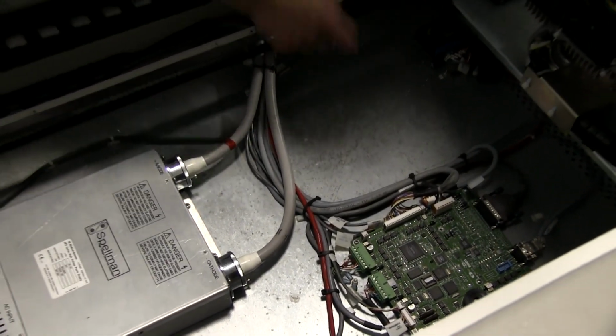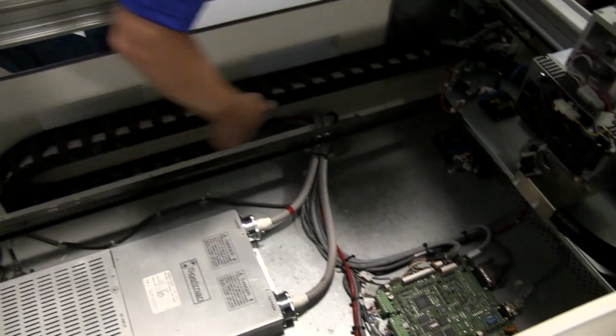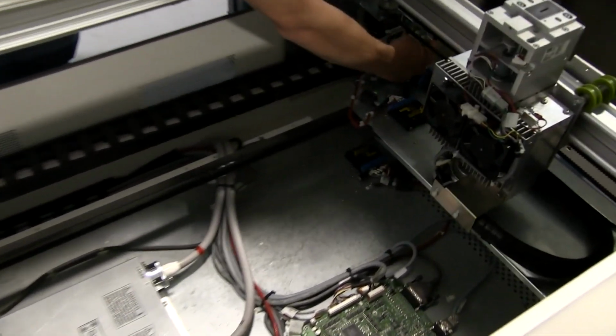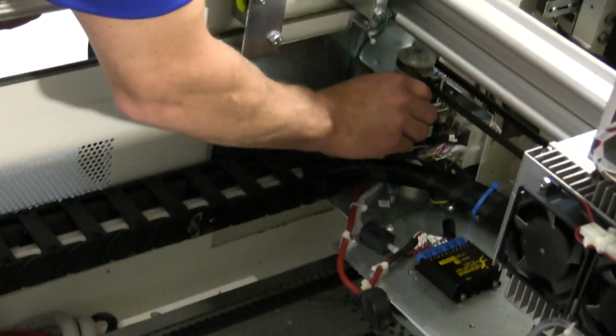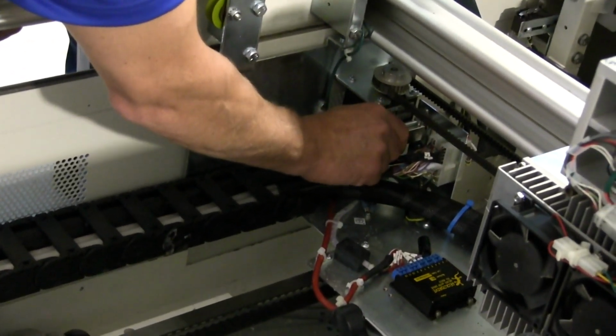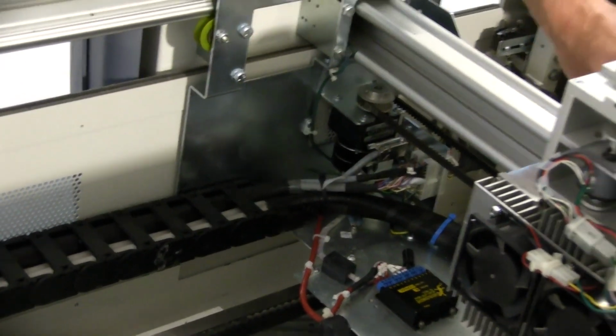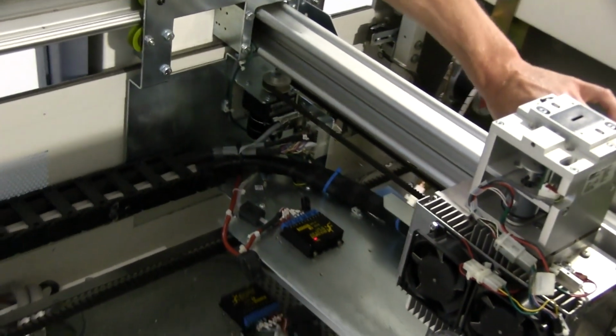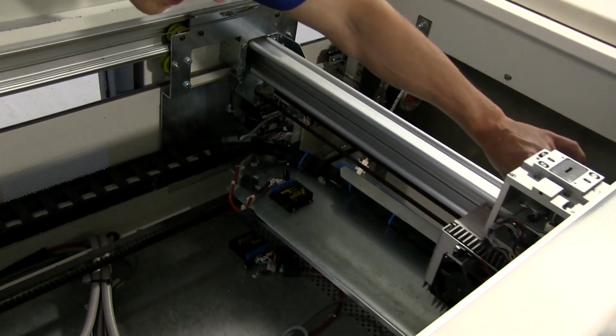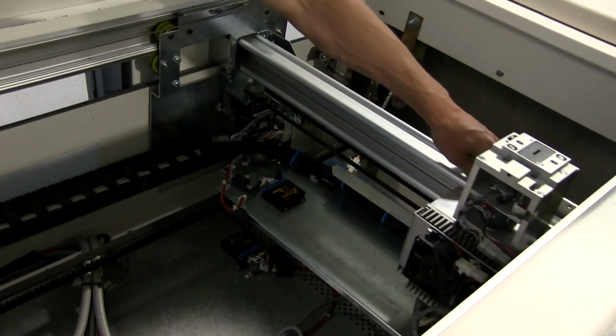Next, we want to look at the cable routing up to the cat track, making sure that your bulkheads are secure and your serial cable. We also want to have free movement for the tube and make sure that our flex is good on our high voltage cables going into the bottom of the tube.